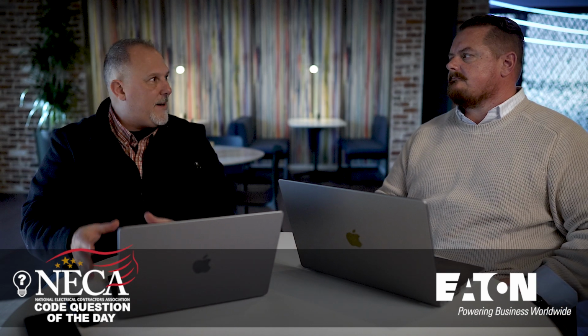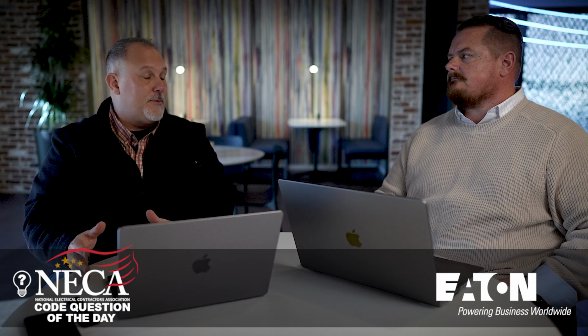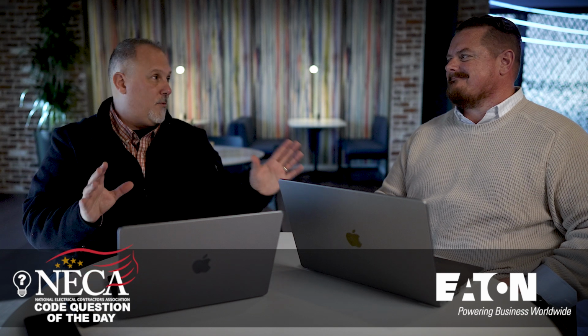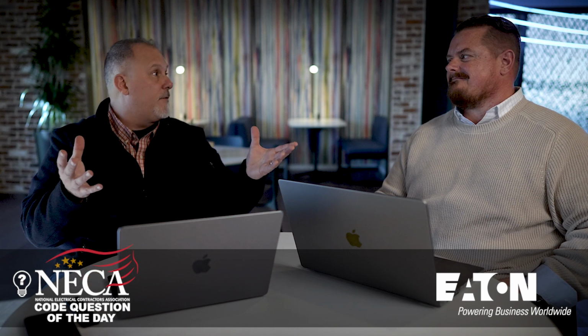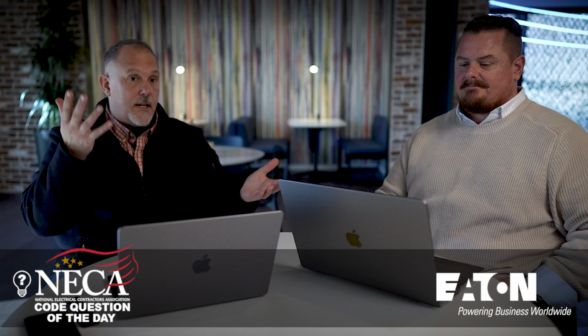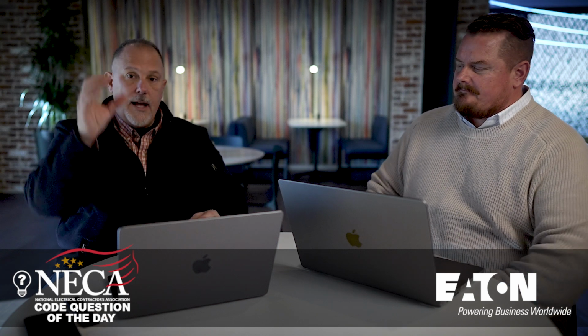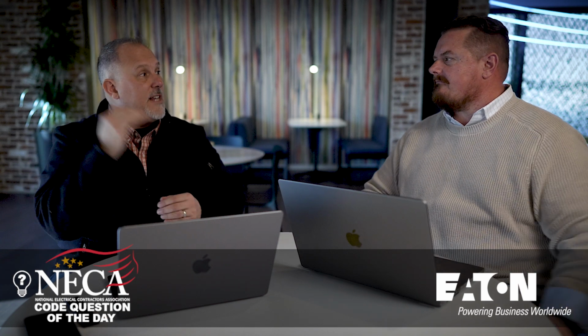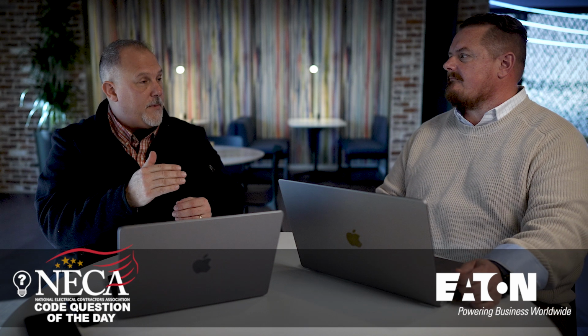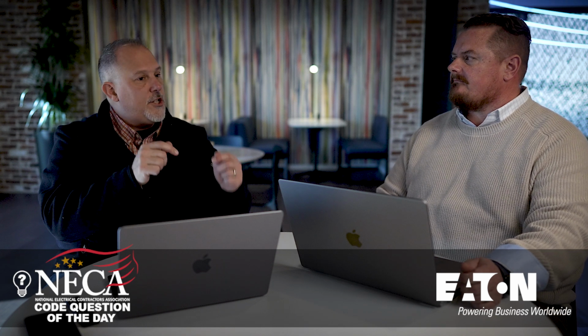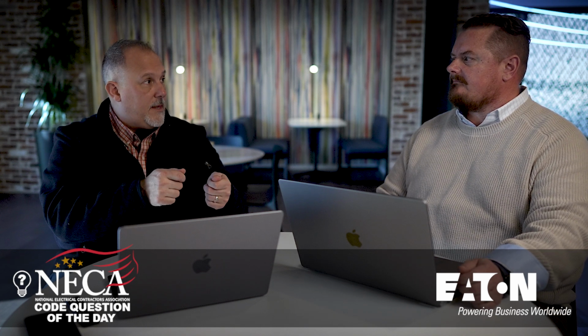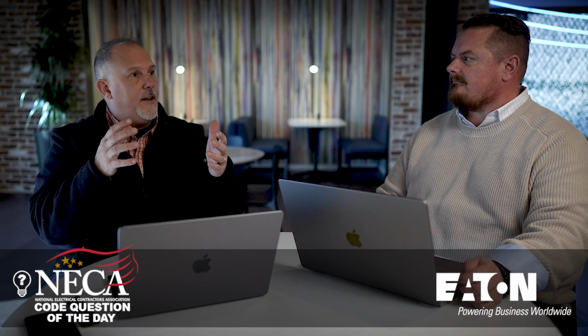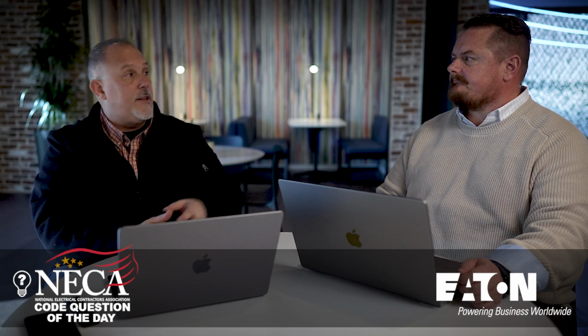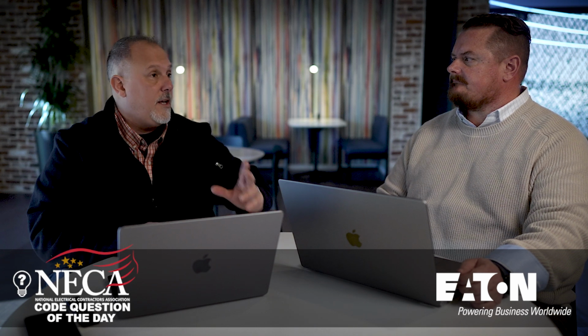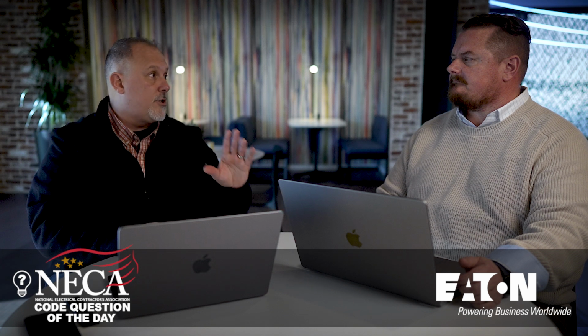Does it still violate 110.10? Absolutely. But we all live in this management of risk world. Yeah. Likelihood and severity. If I can control the likelihood of you establishing an electrically safe work condition, and then the severity, should you be measuring something in that piece of equipment, then from an arc flash perspective, I feel good. The only thing you don't have in that is the shock hazard control.